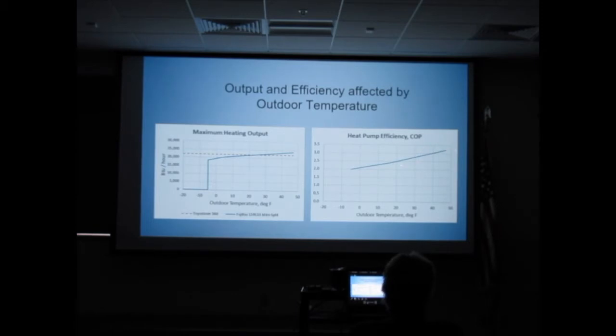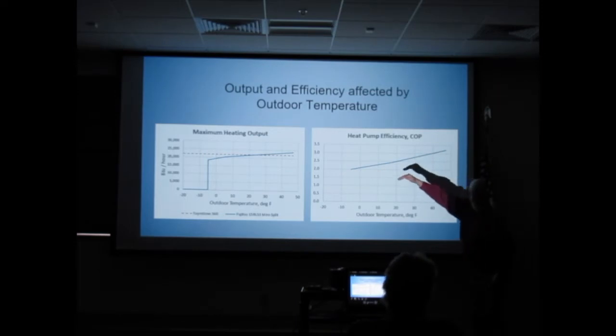Here's what happens to the COP, sort of the same deal. When it's really warm out, we have a really high COP, and as it gets colder out, the COP drops - to a point where even below 0, we're still at a COP of 2, meaning we're still getting twice the amount of energy out of that kilowatt as we would out of the electric heater. Now, this is manufacturer data, so I'd be dropping that down a little bit.